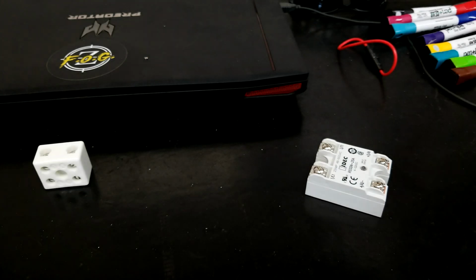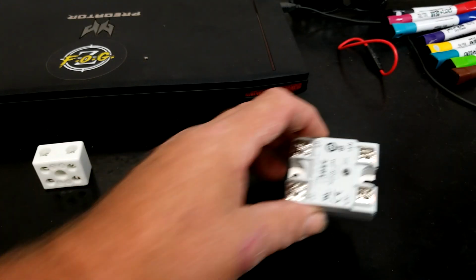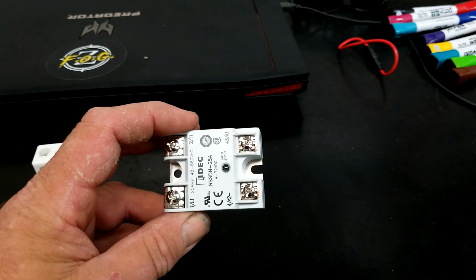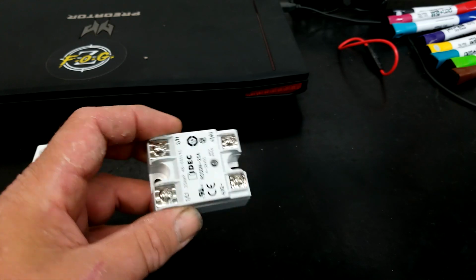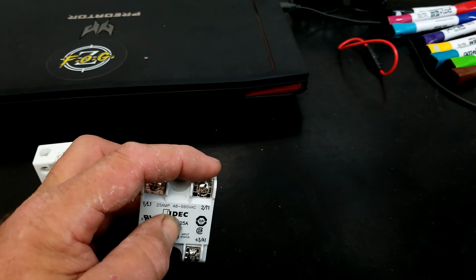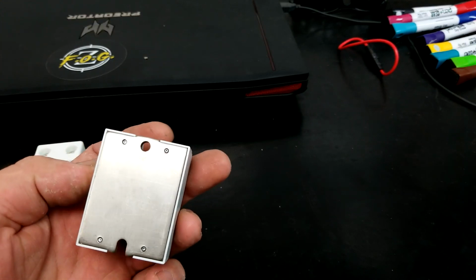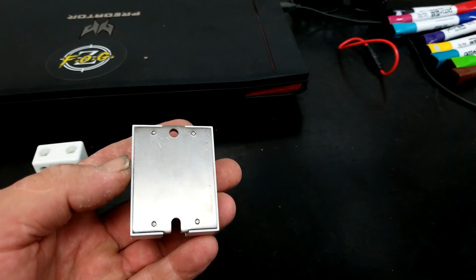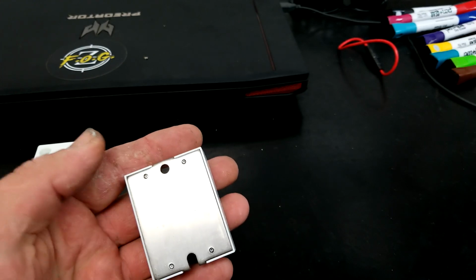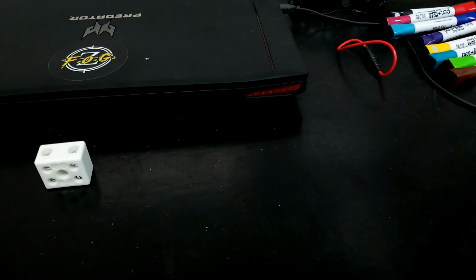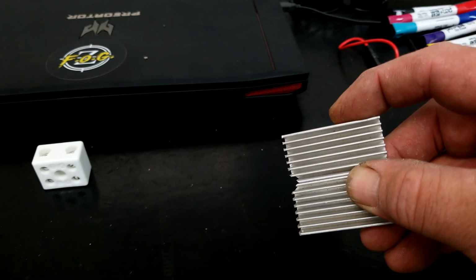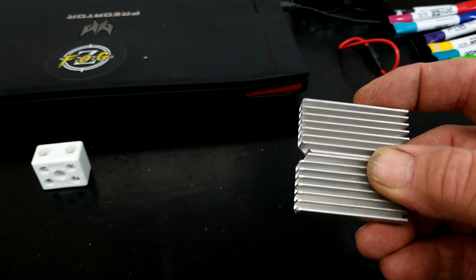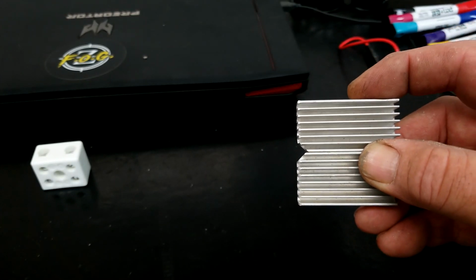Okay, first of all, let's talk about SSRs. This is a little SSR that I use. This is just a single pole SSR, so one line in, one line out, and then a control. So 4 terminals. It's got a metal back. I don't know if that's stainless or not, but it does have some kind of steel back. And this needs to be put down on a heat sink using either thermal paste or the double stick thermal tape.